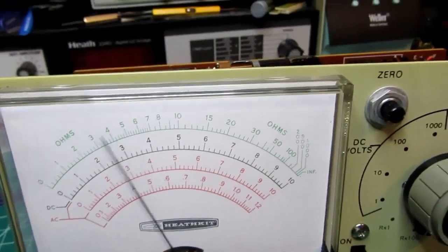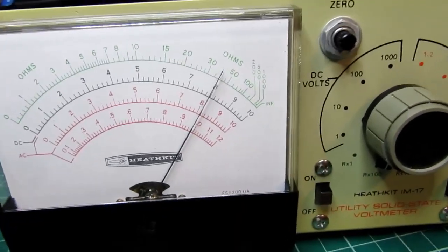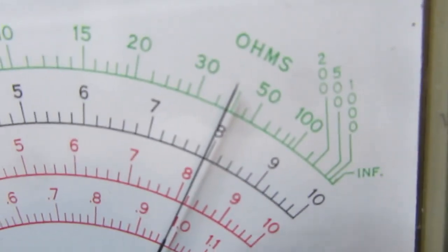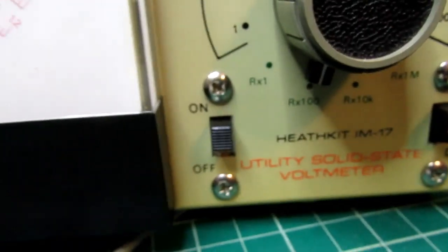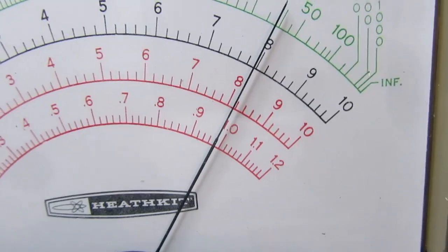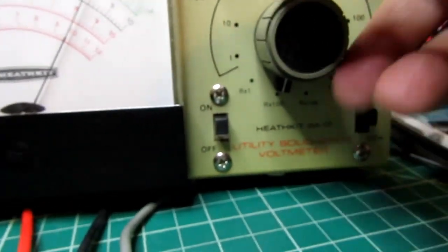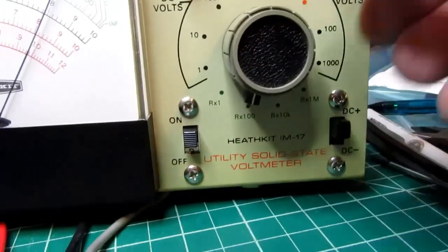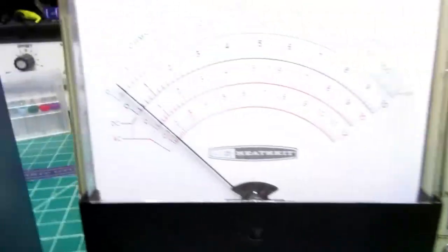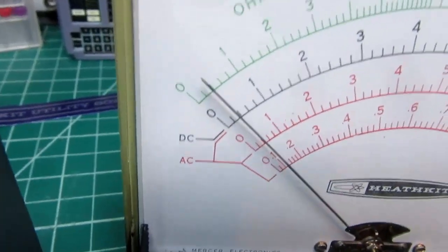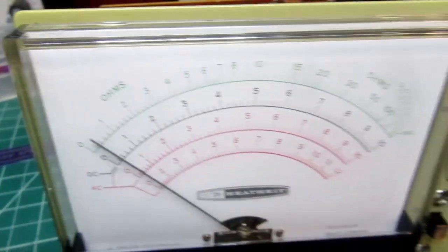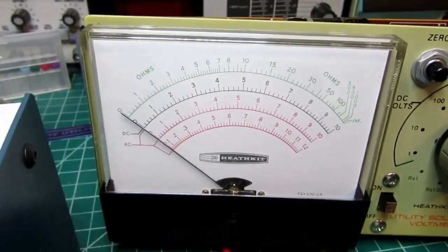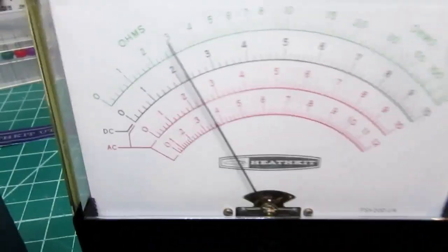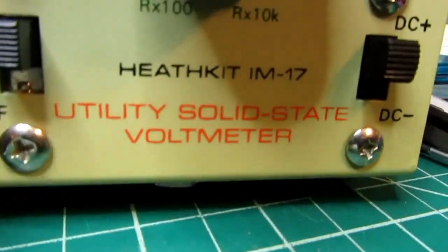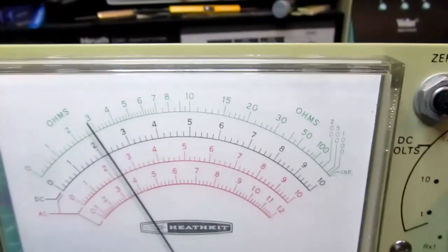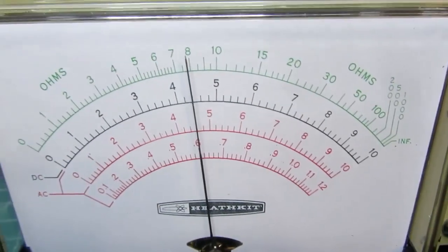Let's try bringing up 4K. Well, it's reading halfway between 30 and 50 times 100, so yeah, it's reading 4K. So that's reading pretty well, but now I can go up perhaps to the 10K range and see what I get there. Well, it's very low, but it's on the low side of halfway between 0 and 1, so it's not doing too badly. Let's try bringing up 30K, and we're on 3 times 10K, so 30K. Let's go to 80, and it's right on.